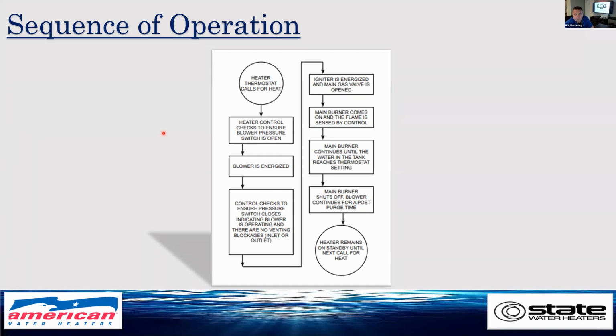So within that sequence of operation, the thermostat will call for heat. The thermostat is located in the gas valve. The heater controls check to ensure the blower pressure switch is open. So it has to prove the switch is open before the blower kicks on and then closes it. Then the blower is energized. The gas valve checks to ensure the pressure switch closes, which indicates the blower is in operation and there are no venting blockages. The igniter is then engaged and the main gas valve is opened. The main burner comes on and the flame is sensed by the controller. The main burner continues to run until the heater reaches temperature, goes into its post-purge, and then remains in standby until another call for heat.